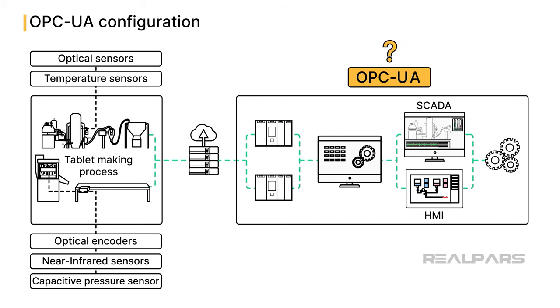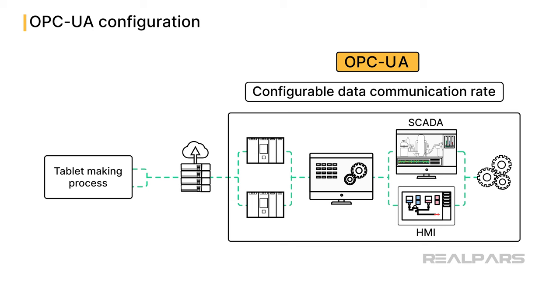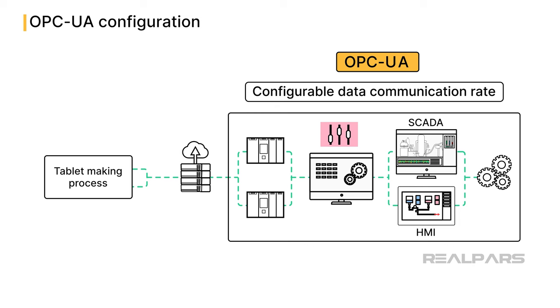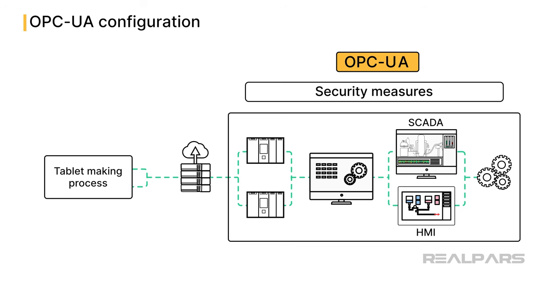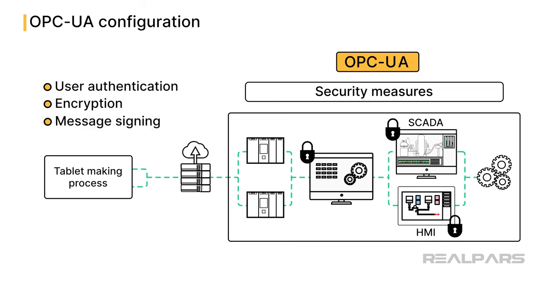So what are the properties that make OPC UA so valuable to the pharmaceutical industry? There are four important characteristics. First, OPC UA has a configurable data communication rate. In pharmaceuticals, rapid changes in conditions can quickly lead to significant batch wastage. Hence, high-frequency data sampling, as fast as 10 milliseconds, can be configured in the OPC UA servers for these applications. Second, security measures are equally as important as data collection rates. Due to the sensitive nature of pharmaceutical data, such as formulas and production rates, available OPC UA security features like user authentication, encryption, and message signing are paramount. These measures also help support regulatory requirements for data integrity.